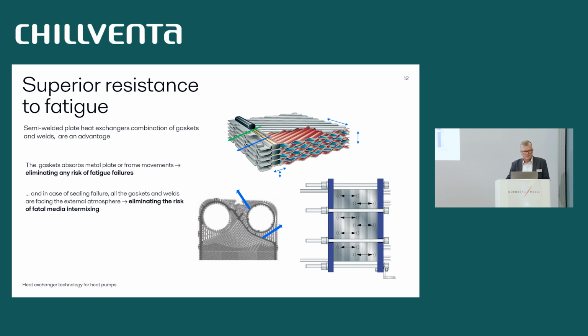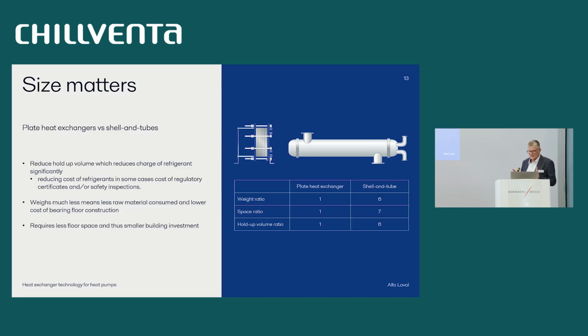These gaskets also mean that we have a superior resistance to fatigue issues. The gaskets absorb metal plate and frame movements. So we will not have any fatigue risk. And if we have any seal failures, it's always external leakage and we are not mixing media, which is fatal. So there's built-in safety, but also size of this compared to shell and tube heat exchangers, for example.